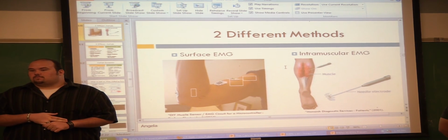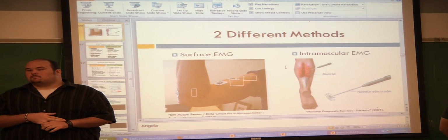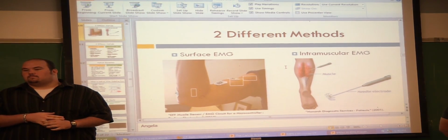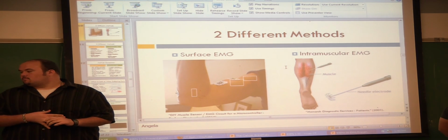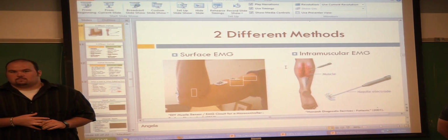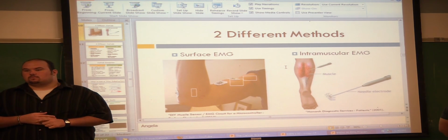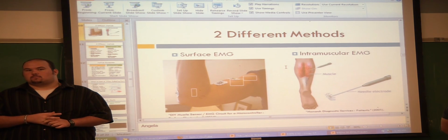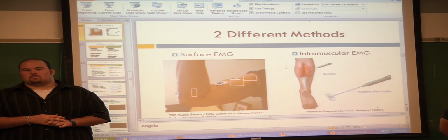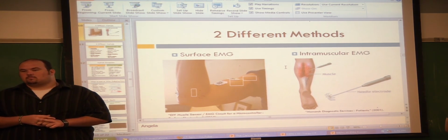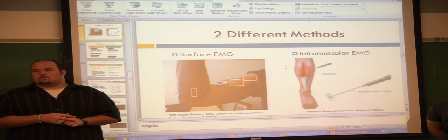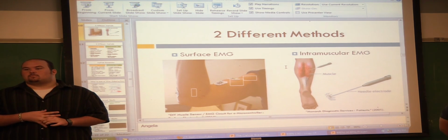I don't know if you know this, but EMG devices usually have a selectable filter for 60 or 50 hertz, because there are countries that don't use 60 hertz. Yes, that's why we show the LabVIEW, so you can actually insert your own types of band stop if you want. They chose the Butterworth for this. As we all know from 130 Lab, there are various ones: elliptical, inverse elliptical, Butterworth, Chebyshev, all kinds of filters you can insert into the system quite easily, for each country and around the world. And that's what engineers' job is, to make these circuits really easy to use.